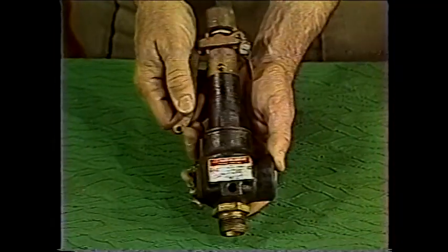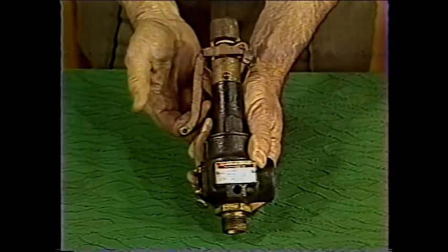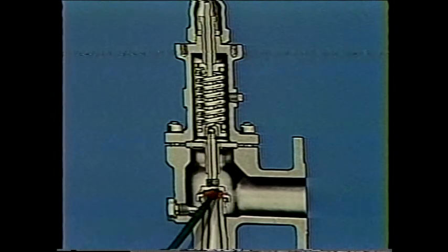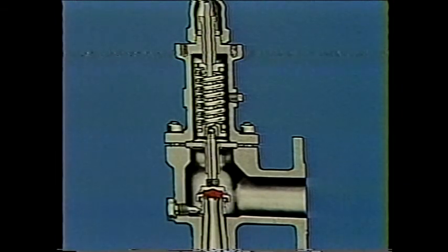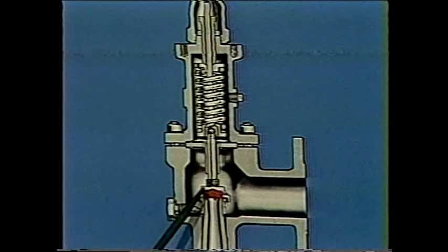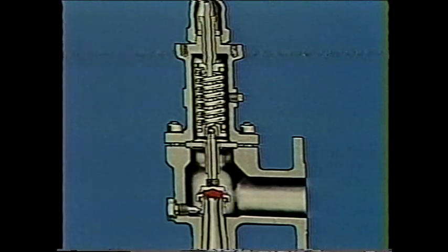Pressure relief valves are essentially angle globe valves, which instead of having a worm and a handle to open and close them, have a spring on top of the disc to hold it on the seat. The pressure is on the underneath side of the disc, here in red, and pushes the spring. When the pressure on this side becomes more than the pressure supplied by the spring, the disc lifts and relieves the pressure. Since the tension on the spring can be adjusted, the valve can be set to operate at some predetermined setting and thus prevent the pressure from becoming high enough to do damage to the rest of the system.